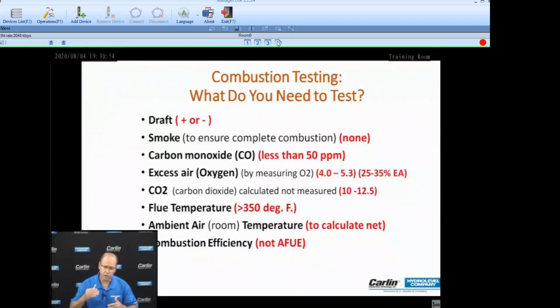I'll put up a slide later on a chart, and you see, and this is where the eyes open up, and it's like, I get it. I understand where these numbers come from and why it makes sense. Carbon dioxide, again, not measured. This is a calculation by, I'm now going to say maybe 95% of the analyzers that are out there. Most analyzers don't have a sensor that measures CO2, but there is a calculation, and based on the fuel that you select, it's going to make a calculation to your CO2 level. The oxygen level will always be true because you have an oxygen sensor in the analyzer. So no matter what fuel you selected for your analyzer, your oxygen level is always going to be what you measure. But if you change the type of fuel, you're going to see that your CO2 level changes because it's a calculation.